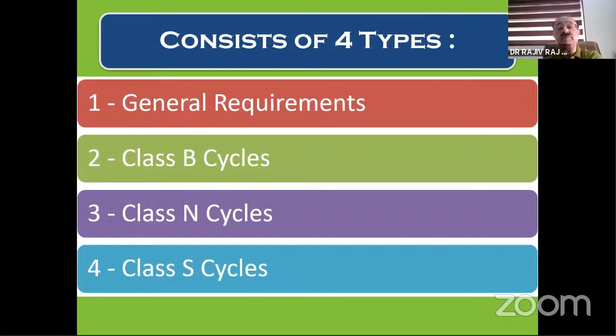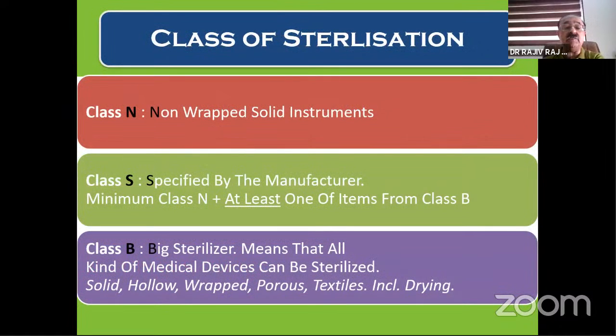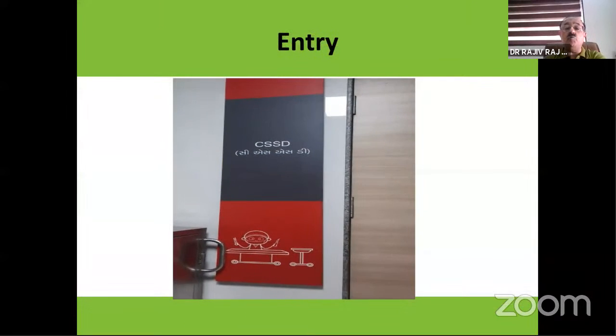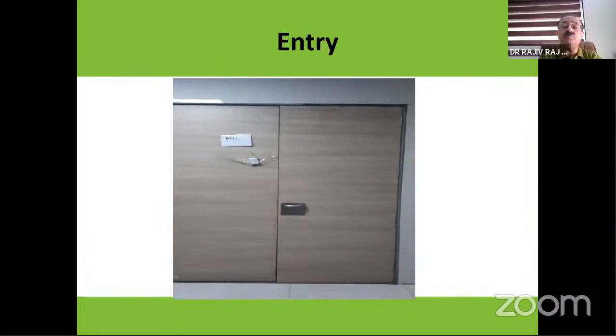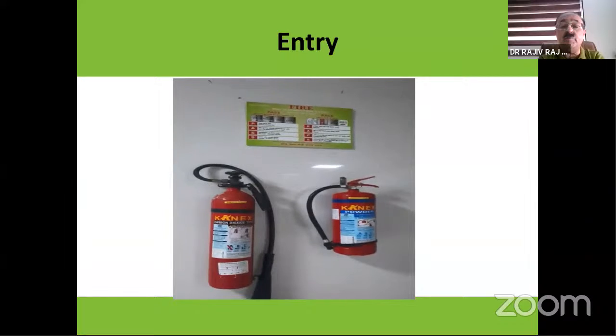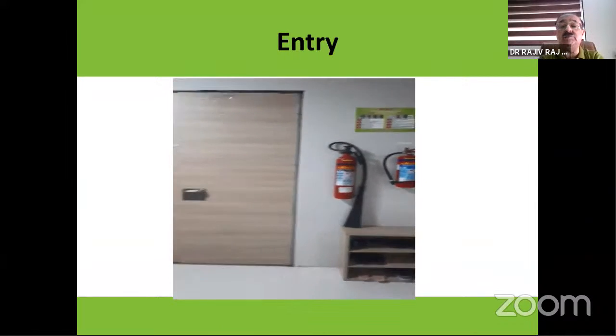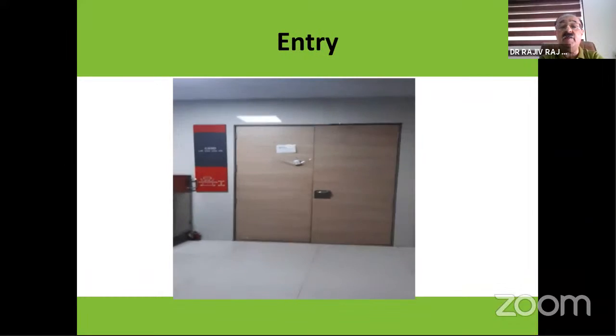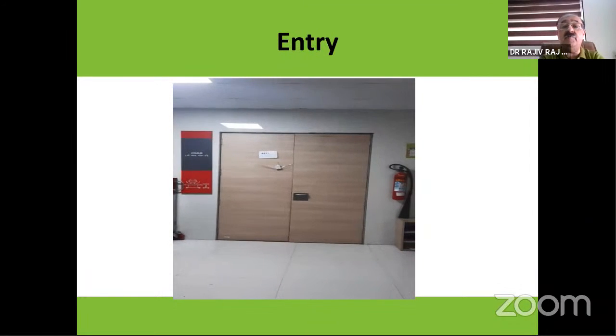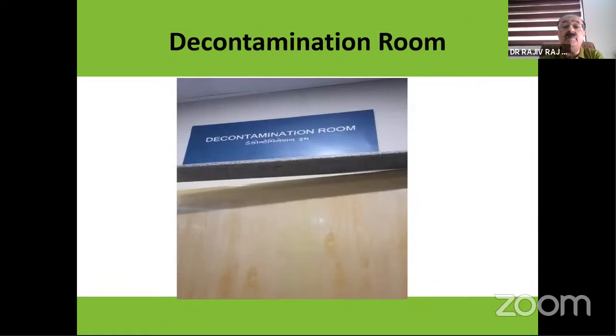There are 4 types of sterilization cycles run in an autoclave: general requirement cycle, class B cycle, class N cycle, and class S cycle. We usually use the class B cycle, which is the big sterilizer, which means that all kinds of medical devices can be sterilized, including drying. So this includes drying. Now, these are a few videos that I am going to show. So one has to be very careful about the fire precautions in this area. So here we have got, it is a very well labeled situation.